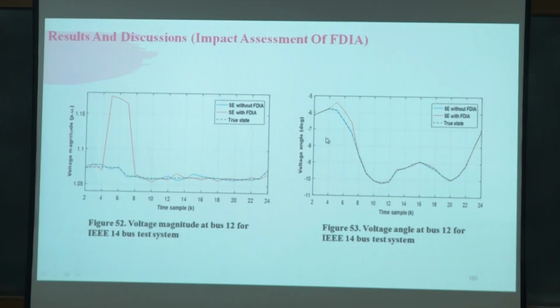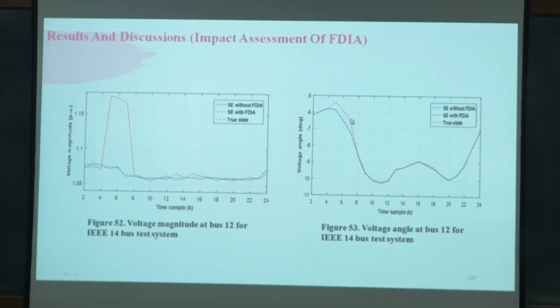Bus number 12 was another bus where the attack was simulated. During the same time steps 5, 6, 7, we find the voltage profile has gone up from normal. This is the normal, true value, without FDIA. So during 5, 6, 7 it has increased. At the same bus, if we see the phase angle, that has also increased during time steps 5, 6 and 7.